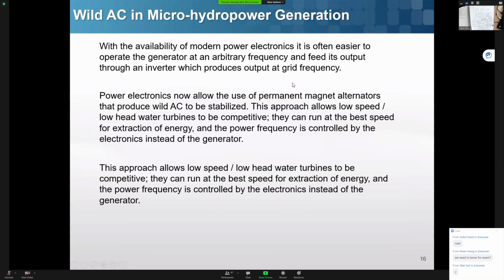So for the smaller generator, you can use a permanent magnet alternator to produce this wild AC. Because the speed of the water flowing might change, your turbine might turn at a different speed, you will generate a different frequency and voltage AC. But then you use the rectifier and inverter, same as we were talking about with the single phase induction generator in the wind turbine. So you will try to convert to whatever is required as the grid frequency and voltage.